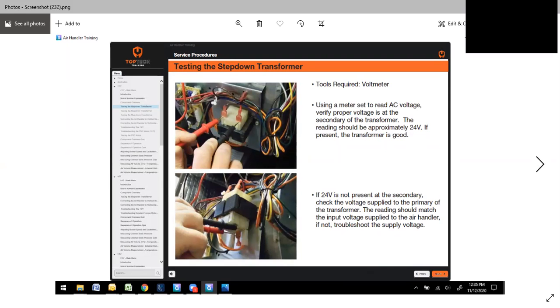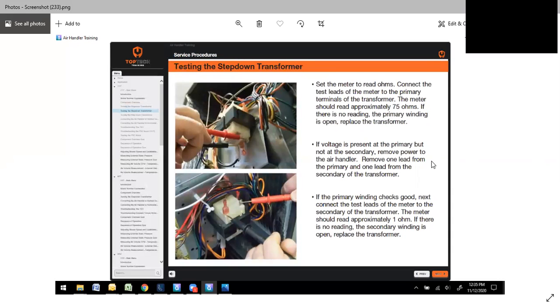But you can go a step further with that. You can also ohm out your transformer. So if you're questioning your primary side, disconnect the power first. Don't do this live. Test the primary side of the transformer, whatever voltage you're using. Once you do that, the meter should read approximately 75 ohms. If there is no reading, the primary winding is open. As long as you have approximately 75 ohms, it's a good transformer, a good primary. If it's open, replace the transformer.